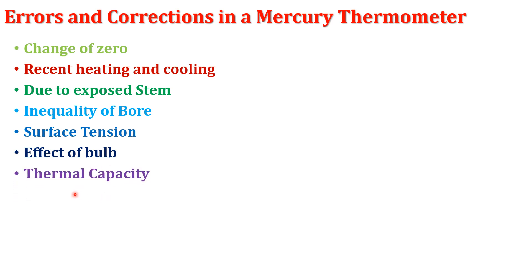The last error is thermal capacity. If the thermal capacity of the bulb is large, part of the heat is used in heating the glass bulb, so the thermometer reading will always show a lower value. To correct this error, a small bulb with lower thermal capacity should be used to get accurate readings. These are the different errors in the mercury thermometer and how we correct them.